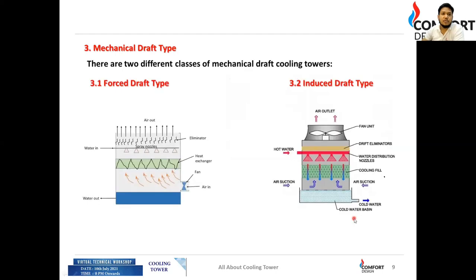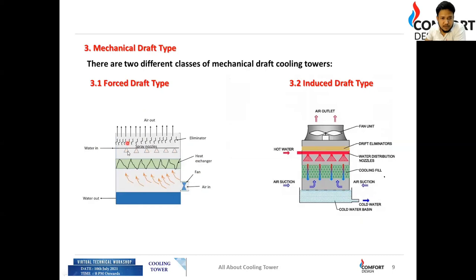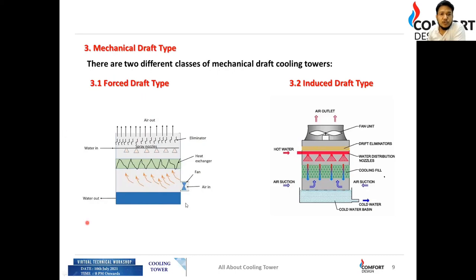The third air draft type is mechanical draft, which includes forced draft and induced draft towers. These are the types used in HVAC applications and can be either cross flow or counter flow. In a forced draft type, a fan forces air through a heat exchanger. Hot water drizzles from the top, comes in contact with the air, heat is transferred, and the cooled water is accumulated at the base for use in the application.